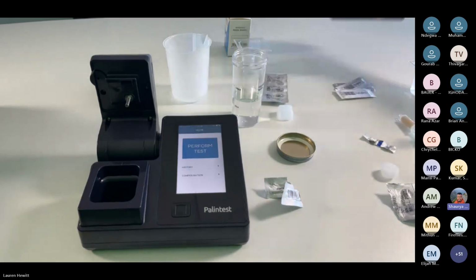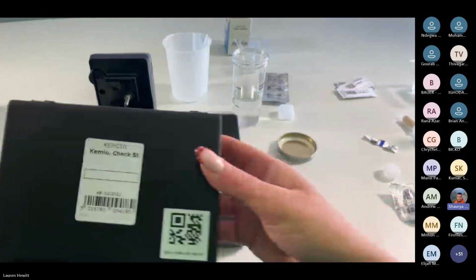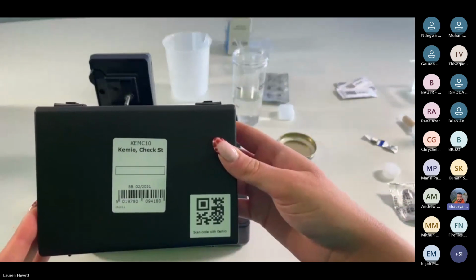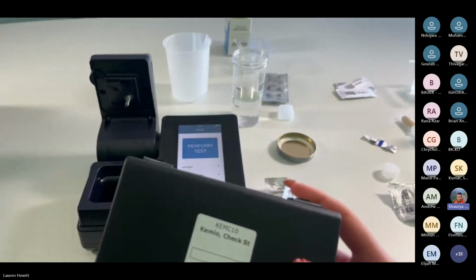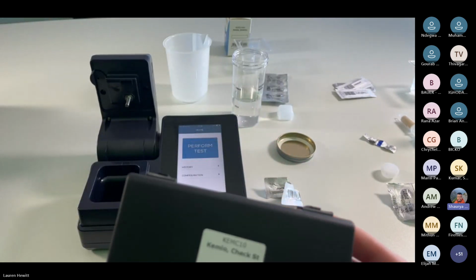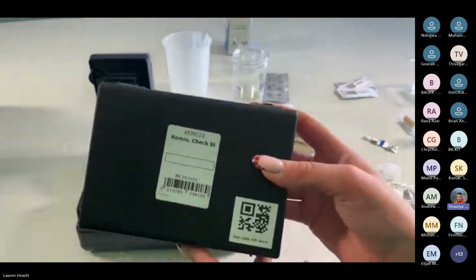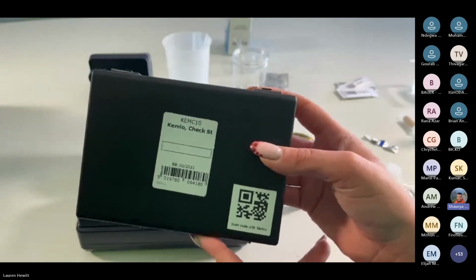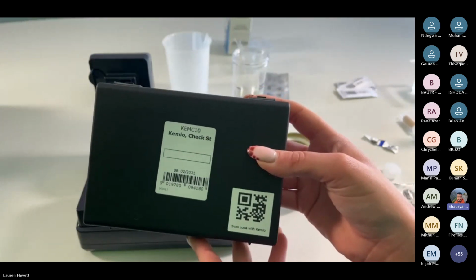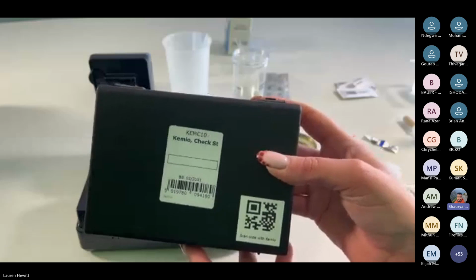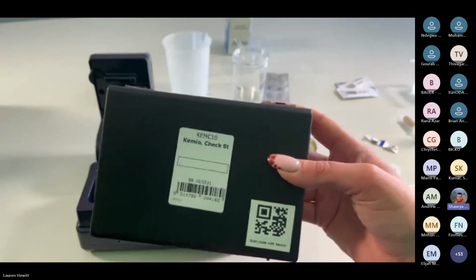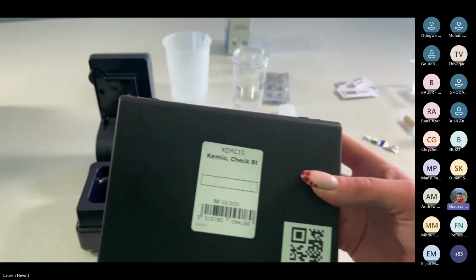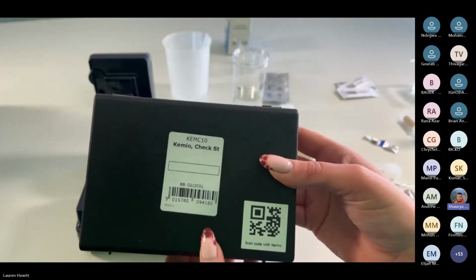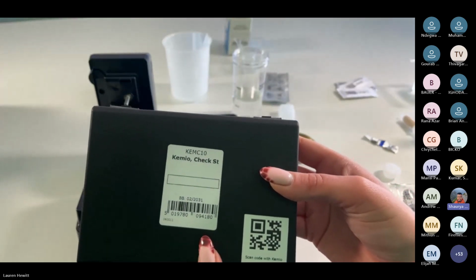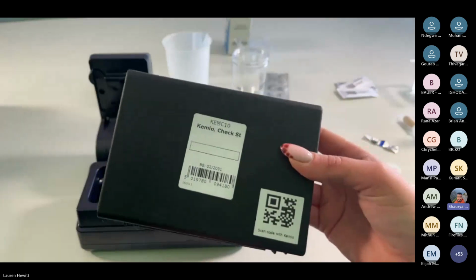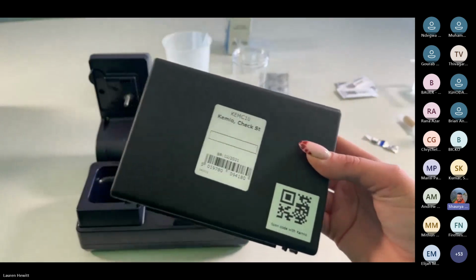Just before we jump back onto the presentation, I wanted to share that Kemio check standards do come as part of Kemio kits, and they are used to verify the calibration of the instrument between annual servicing. They are simply 3 metal conductors; the instrument applies a known voltage and measures the resultant current. If any of these are outside of range, it will show on the screen, and that could be a sign of contamination of the contact pads or the check standard itself, or that the instrument is due a calibration if it is outside of that annual servicing. But we have more details on that, and I'll pass back over to Sharia for the presentation.